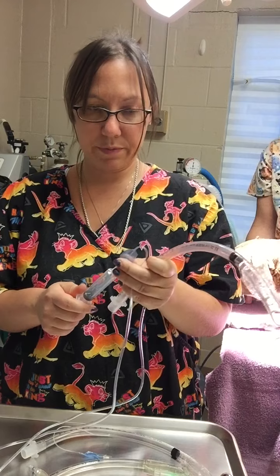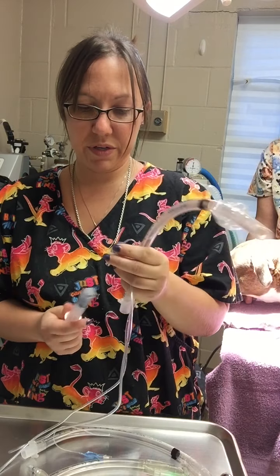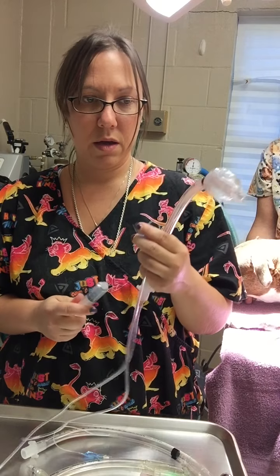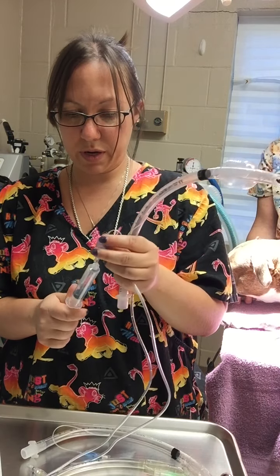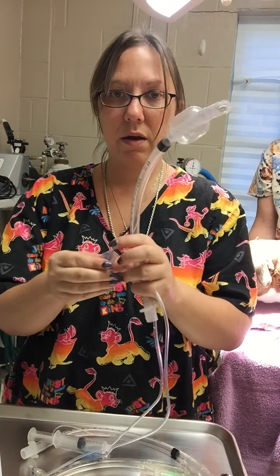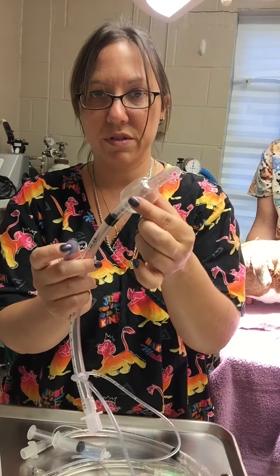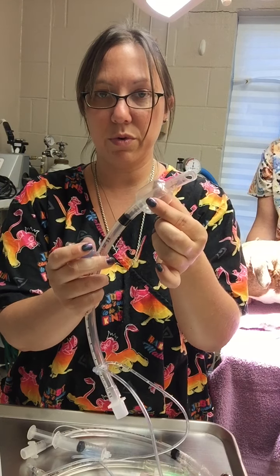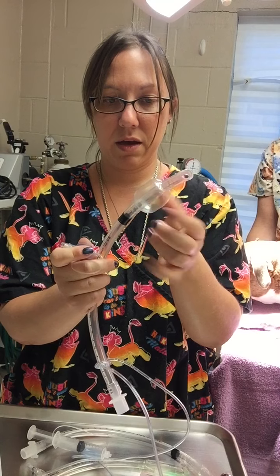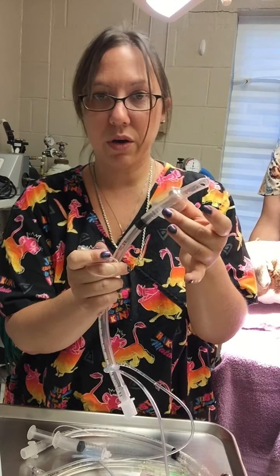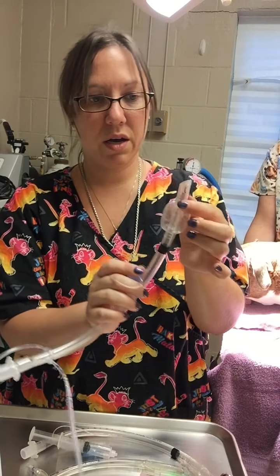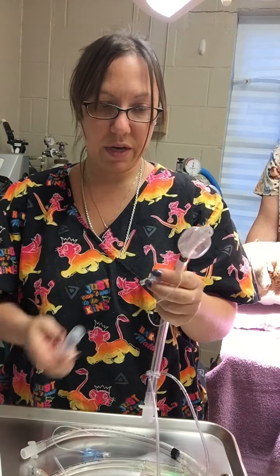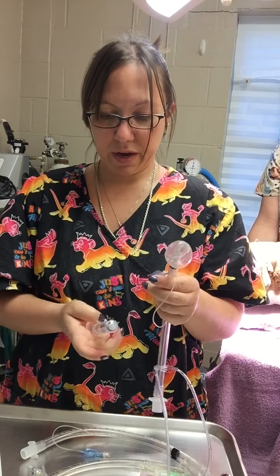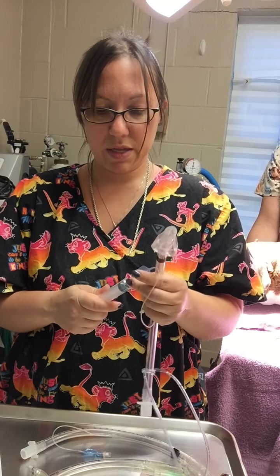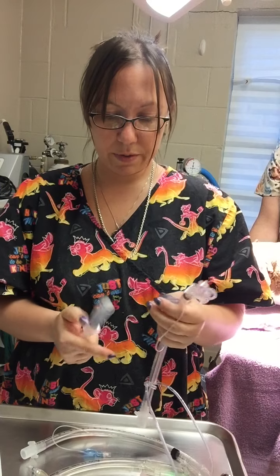I'm going to inflate the cuffs. As I do so, I'm going to be palpating the cuff right up in here, and then as I palpate here, I'll be able to feel a pressure as well as feel that in the balloon as well. So as I push down, it'll push more of that air there. I'm not seeing anything deflate, so I have some pretty good pressure and resistance. There's no gunk on the edges, so I'm also checking for that. So that tube looks good. If I were concerned about a leak, I could take a bowl of water and submerge the balloon into that bowl of water and look for little air bubbles.